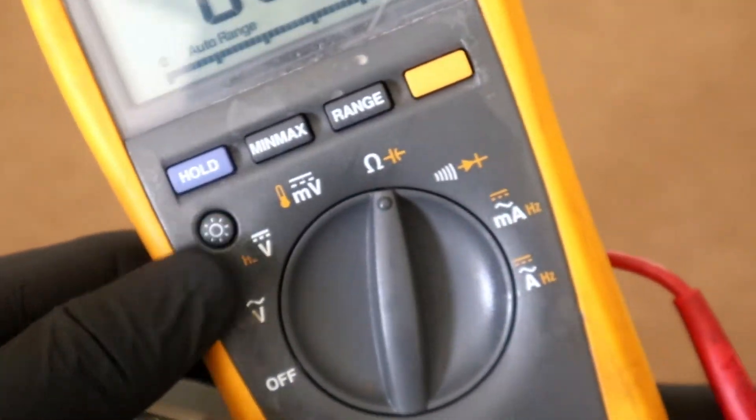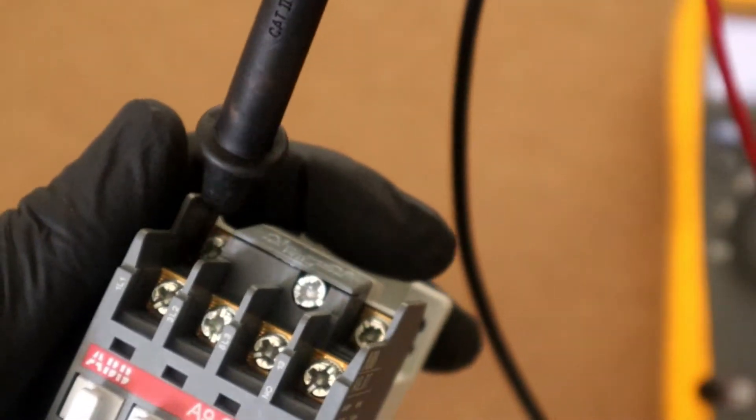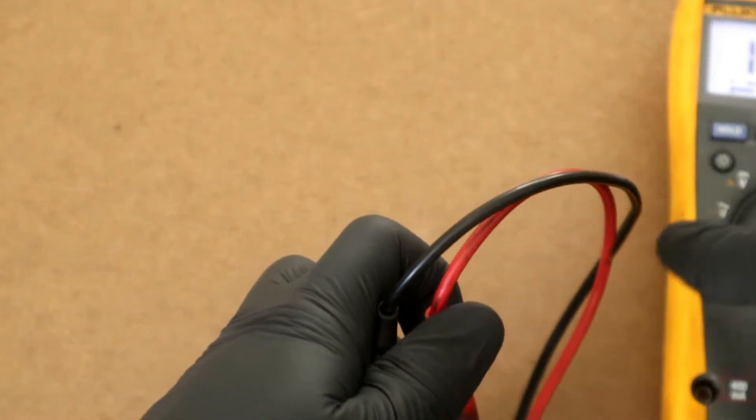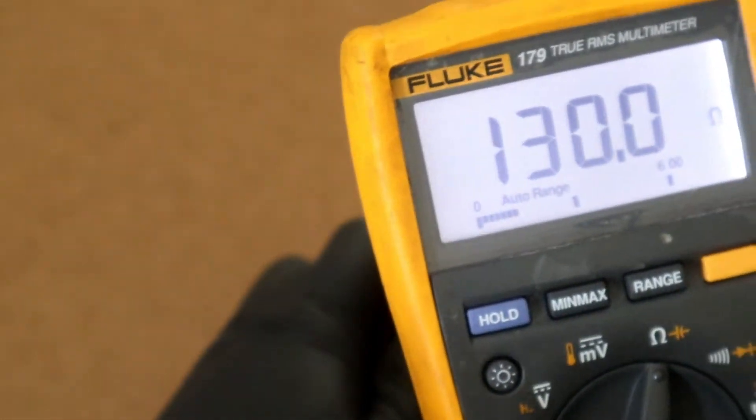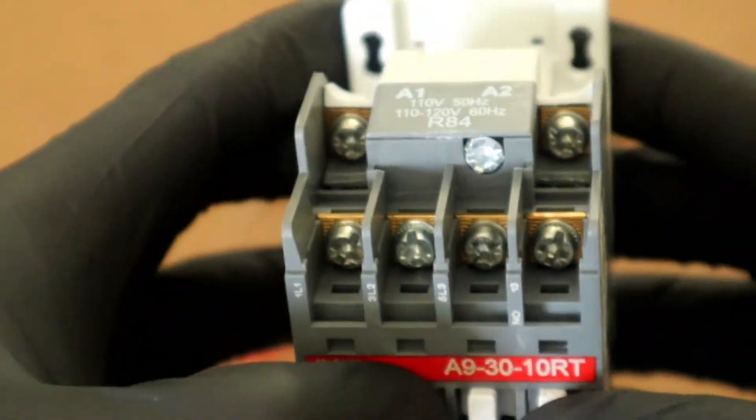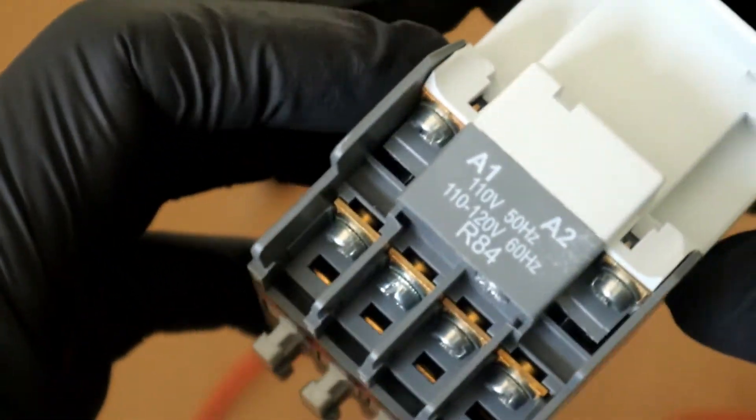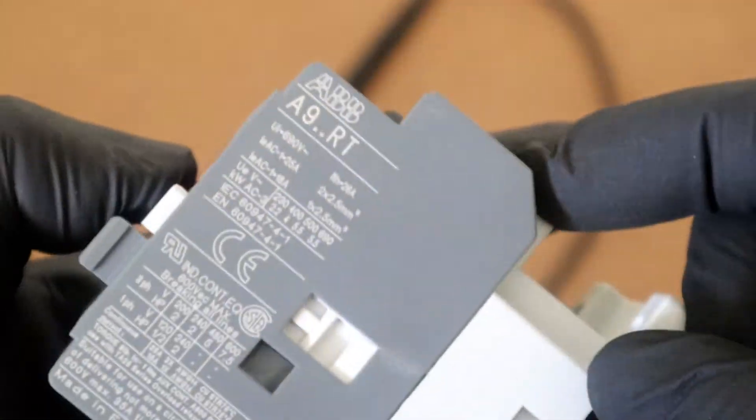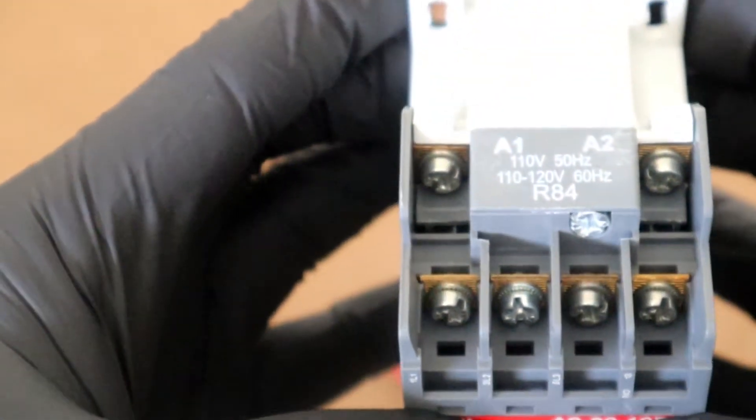We'll continue to test, verify that our multimeter is in the ohm position. We go across A1, A2 and we have 130 ohms. For a contactor like this, I've worked with a lot of them and I can testify that having that particular resistance, this coil is perfect. That's how it comes out of the box, 130 ohm coil. This contactor has passed our contactor tests and it's good to be installed in whatever circuit you need.